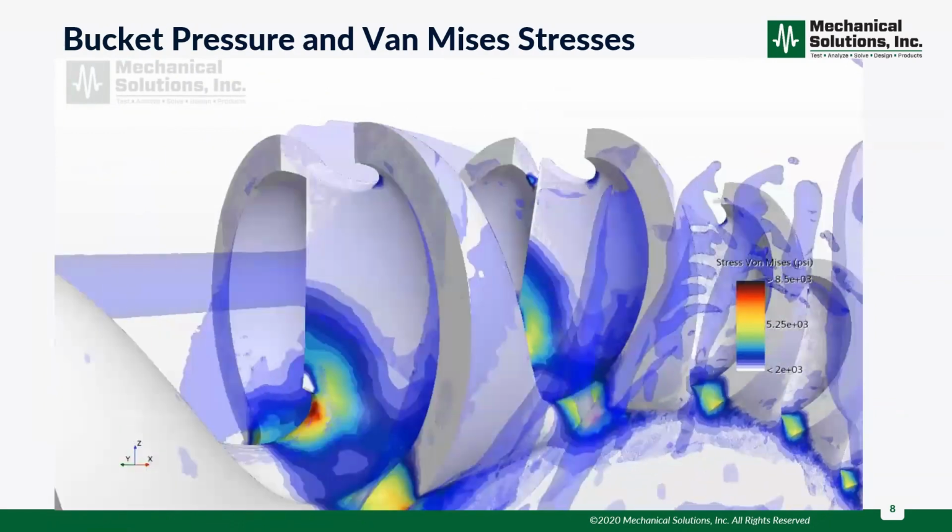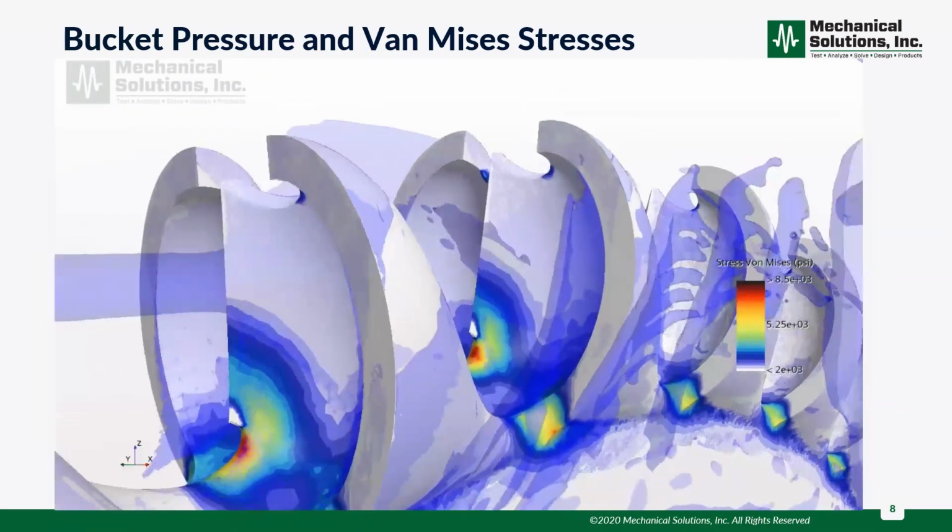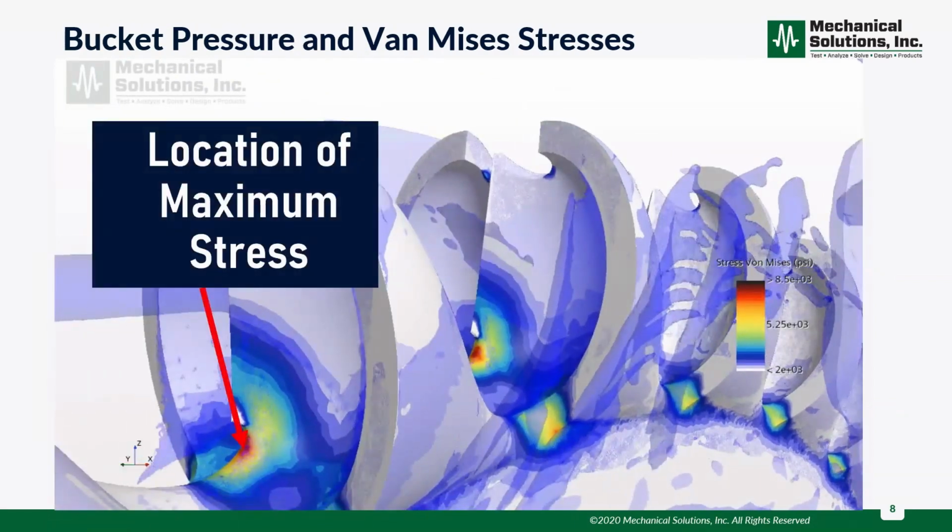I also noticed that actually van Mises should be von Mises, as two different spellings. And here at the bottom of the bucket, where the arrow is pointing, where you see the high stress area, that is a typical area of concern for Pelton turbines. That's normally where the highest stress occurs. So there is a base load simply because of the centrifugal stress, but then there's a peak load when the jet hits the bucket.